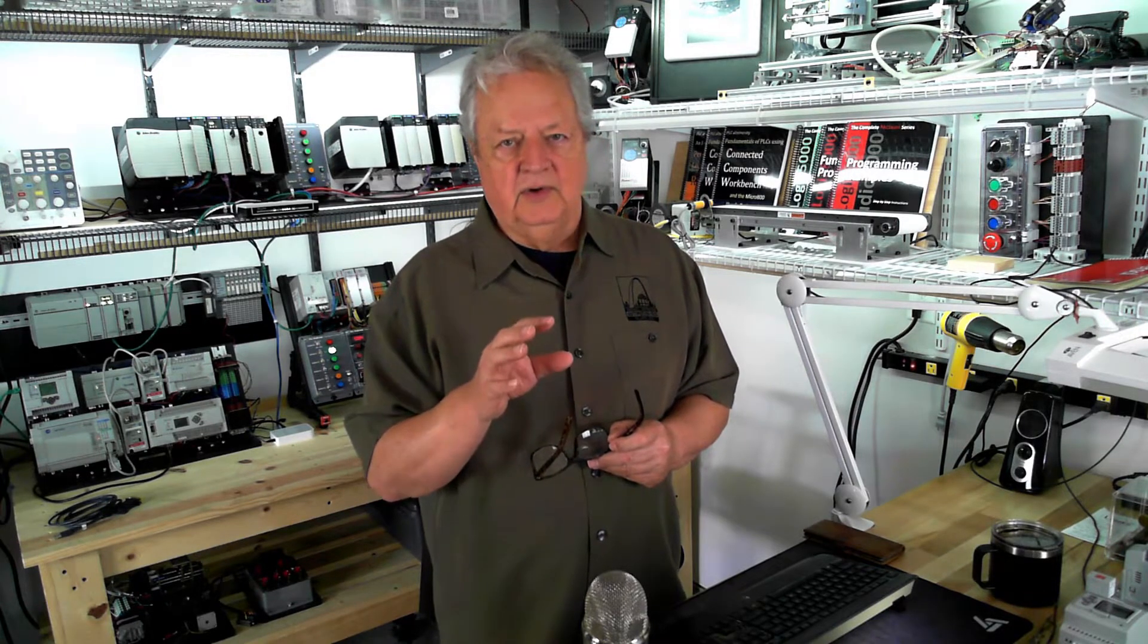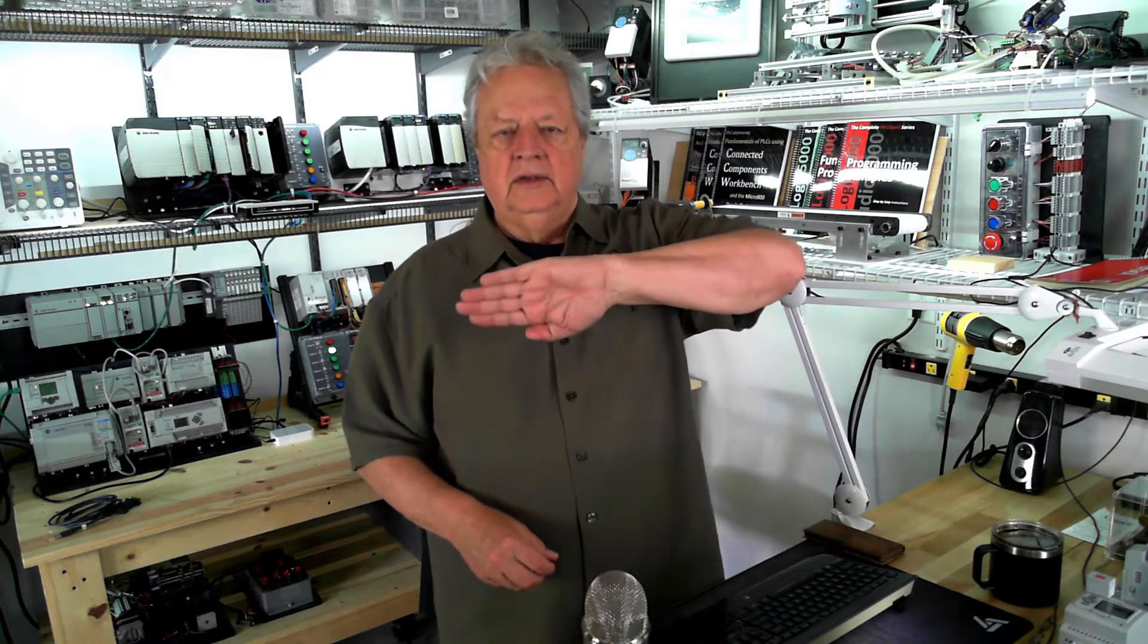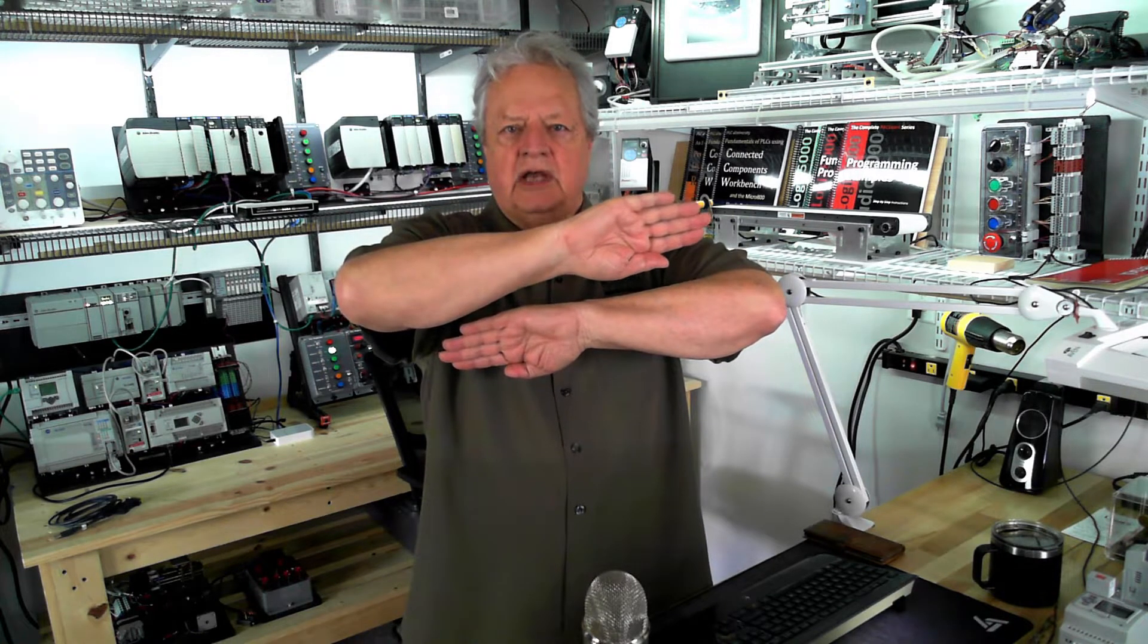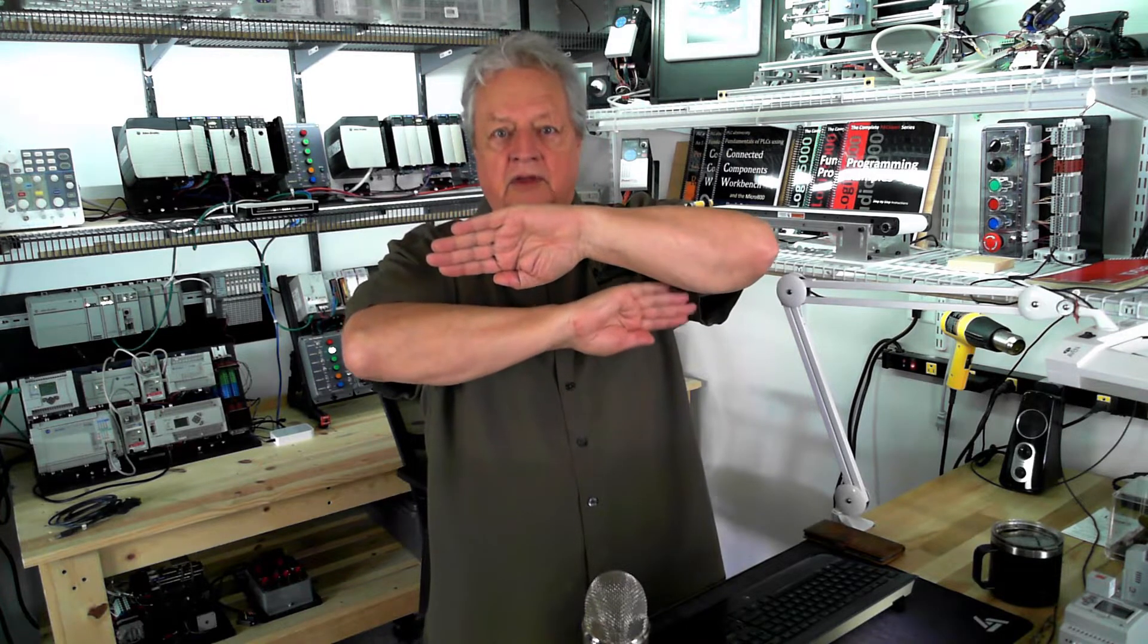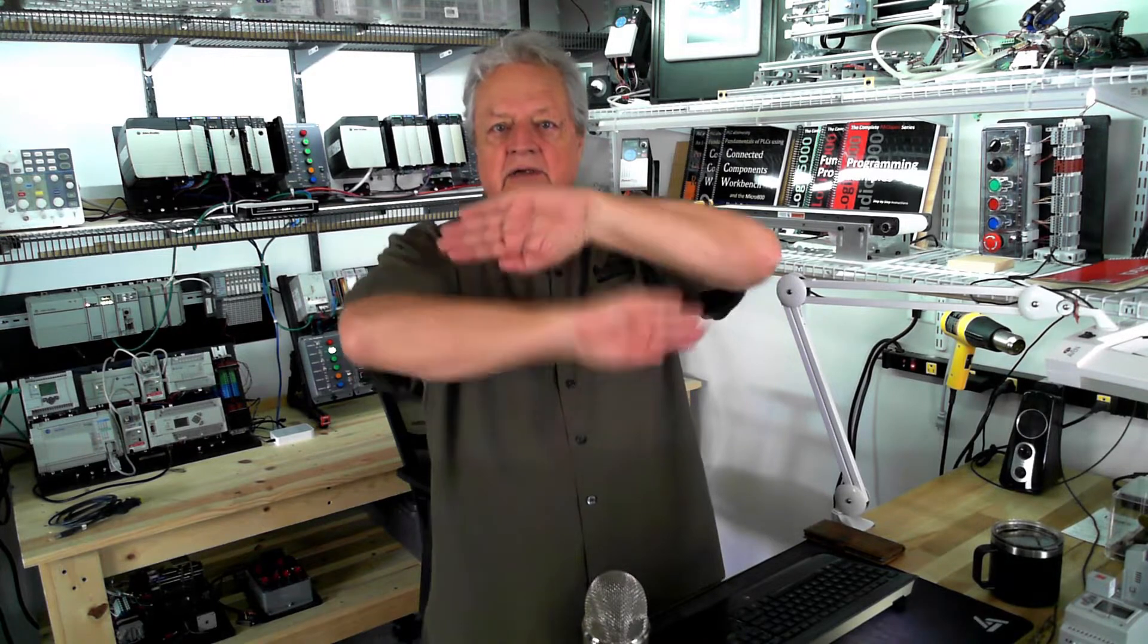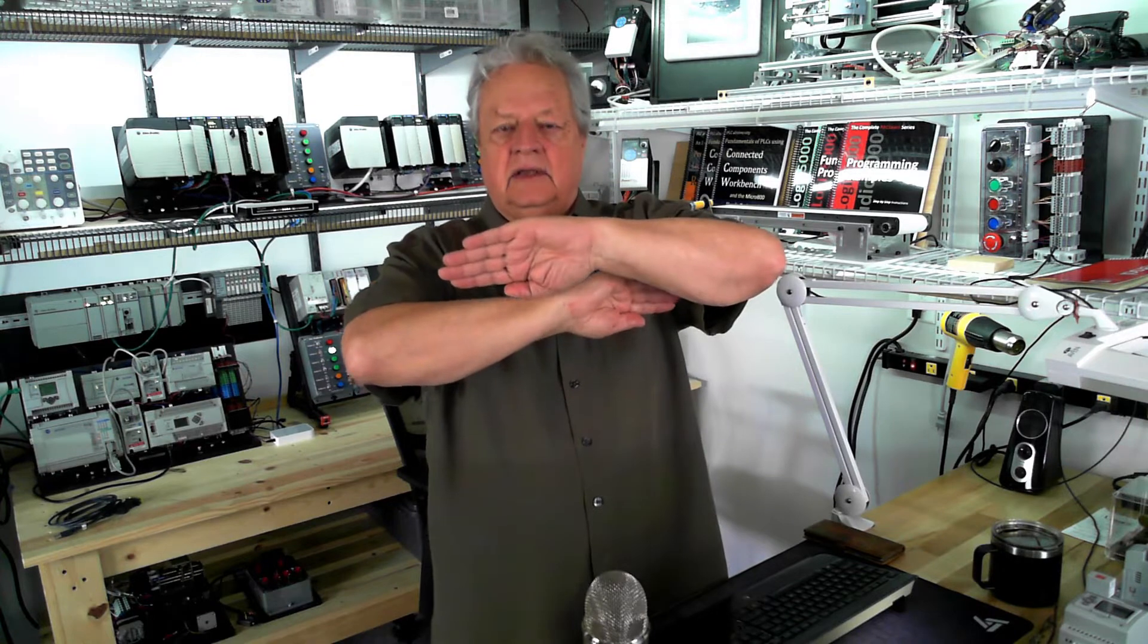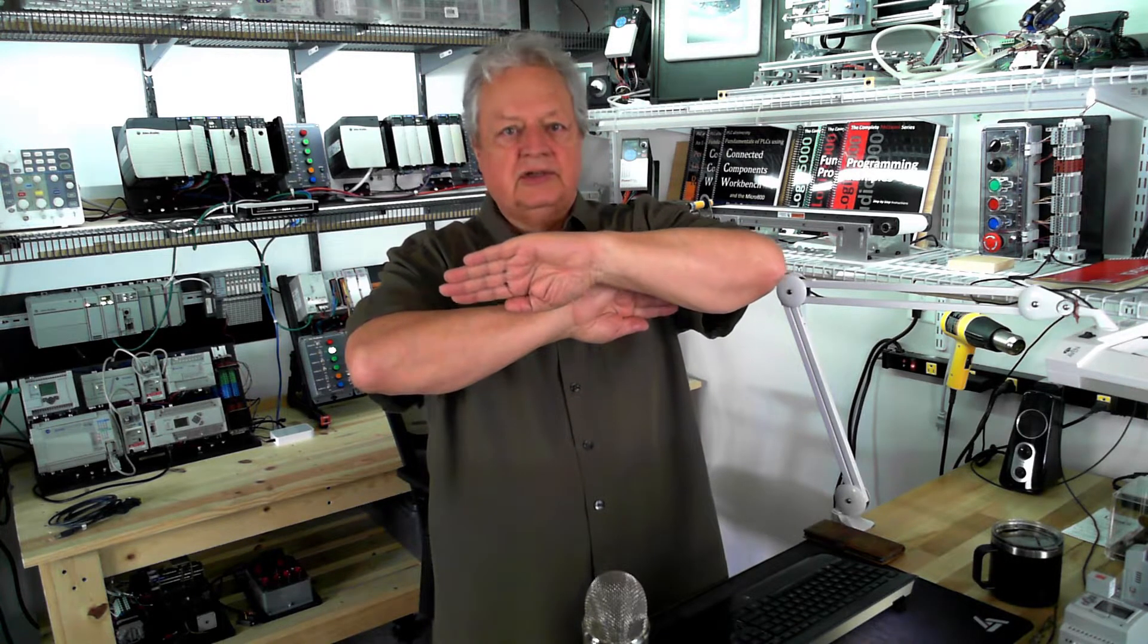Then you go into test mode. You've got two rungs—the one that's being run and another one that you're editing. When you go in test mode, it's now running the one that you've edited. If you decide you don't like that, you click untest and it goes back. But if you test it and like the way it works, then you finalize it.